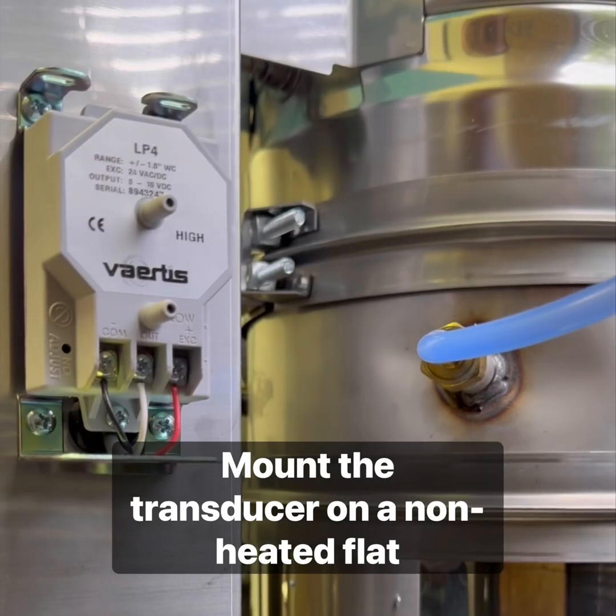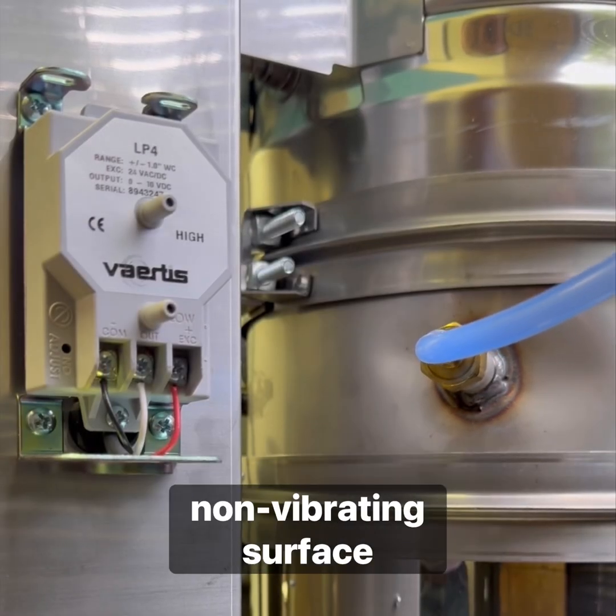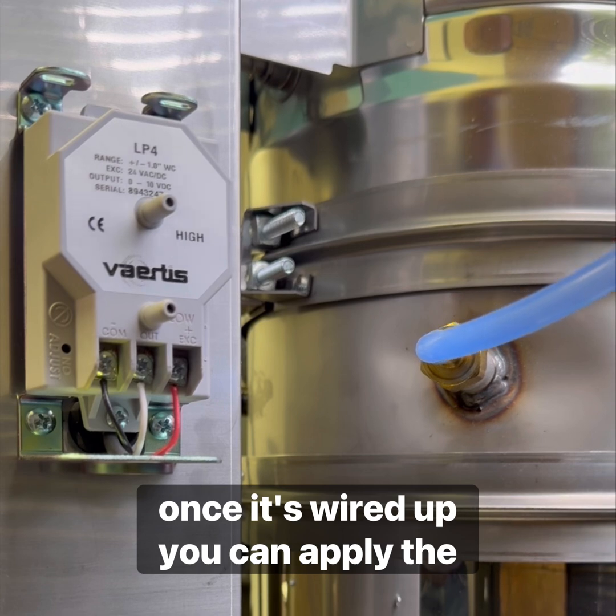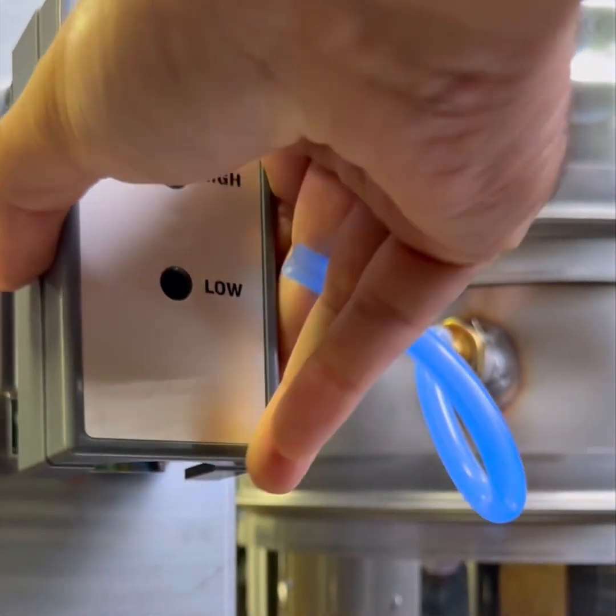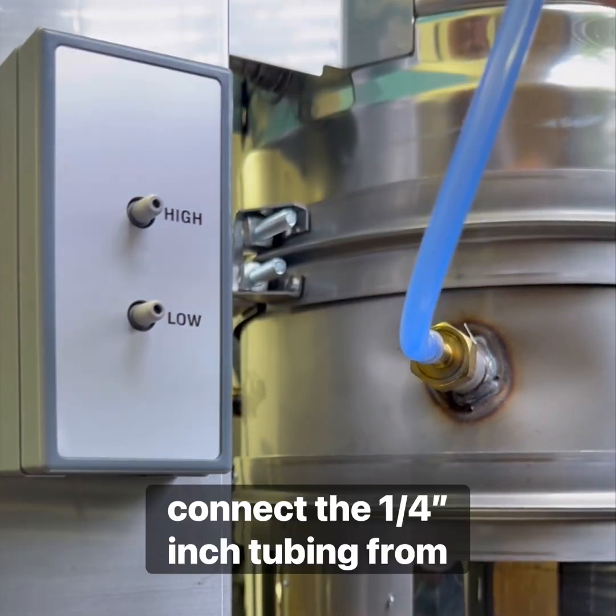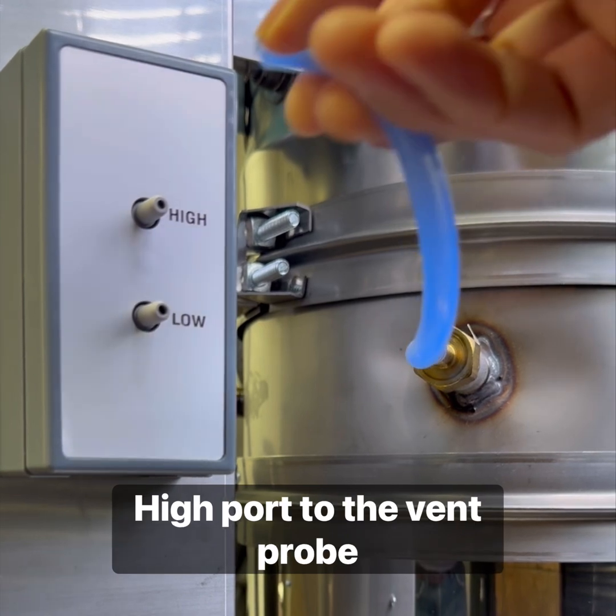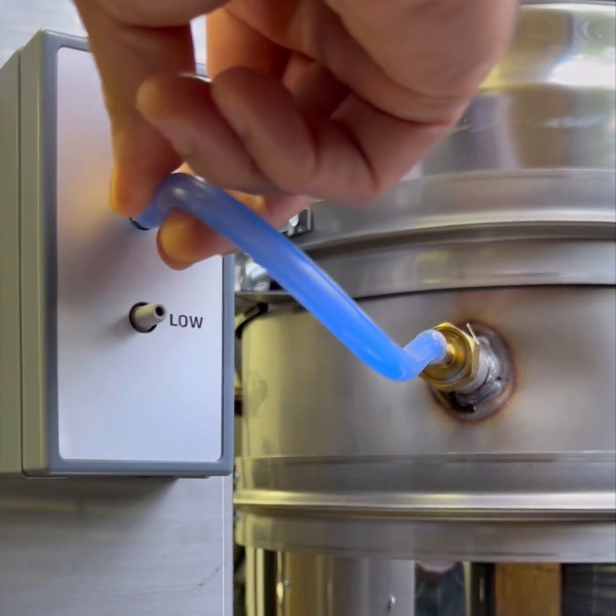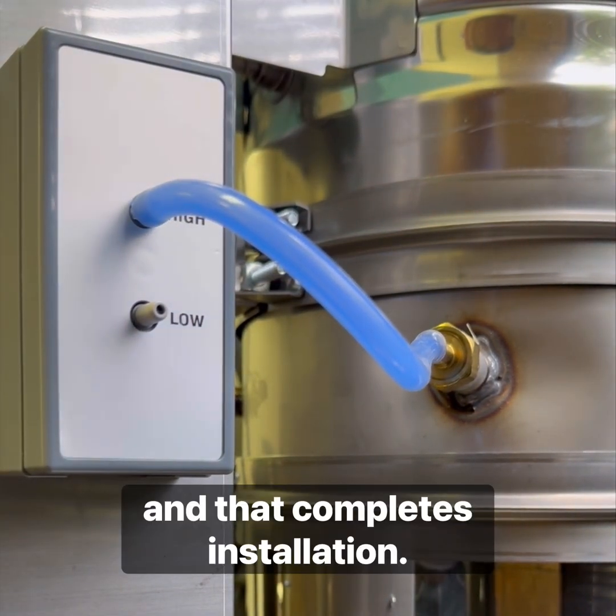Mount the transducer on a non-heated, flat, non-vibrating surface. Once it's wired up, you can apply the housing over the transducer. Connect the 1/4-inch tubing from the high port to the vent probe. And that completes the installation.